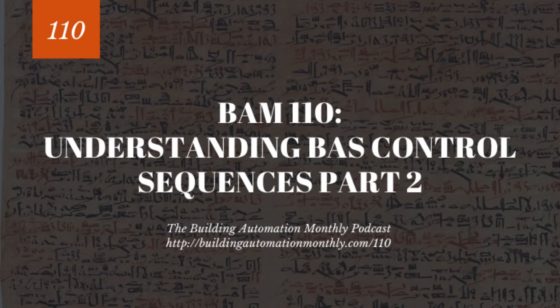cool. Now, on the flip side, you have heating, right? And heating, here's how VAV units work before I go through that. VAV units will tend to be cooling only units on the interior of the building, unless you have a specific reason for heating. For example, maybe you have some equipment that can't get too cold or whatever. Or maybe you have a space that is very temperature sensitive. Maybe it's an operating room or something like that.